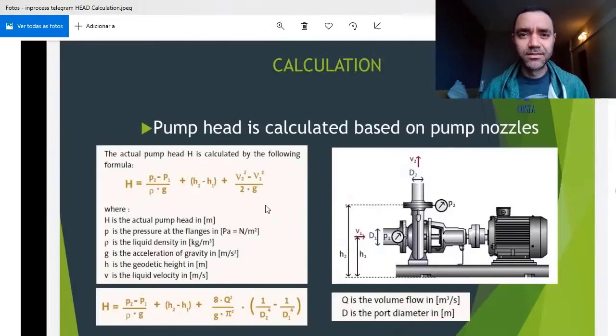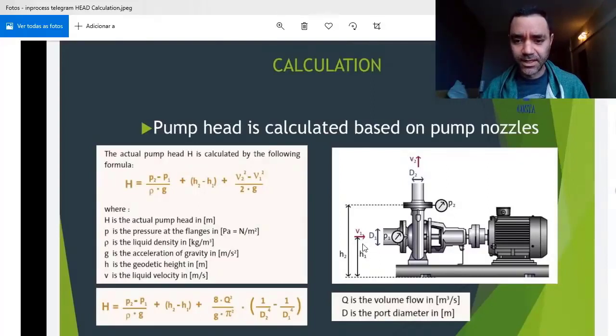But for the head calculation, what you use is this equation here. It takes into account the pressure at the discharge of the pump, the suction of the pump, and there is the elevation related to the center line, as we have seen in the schematic that we just looked at.